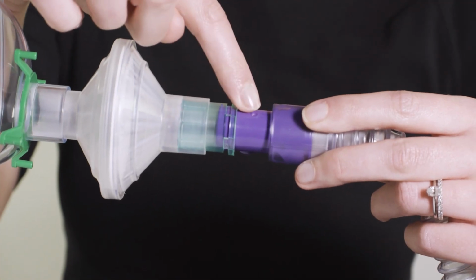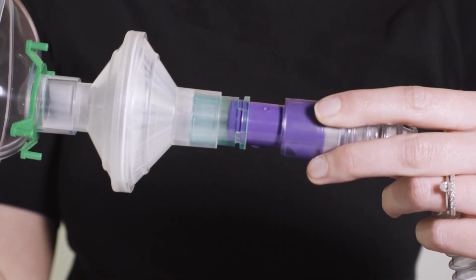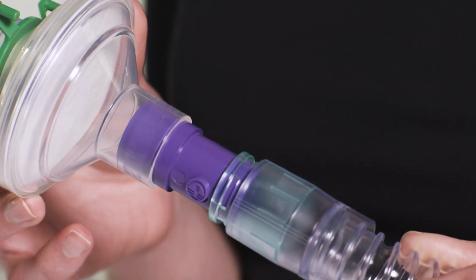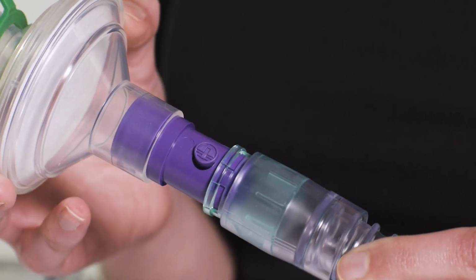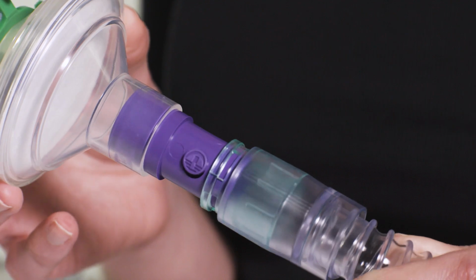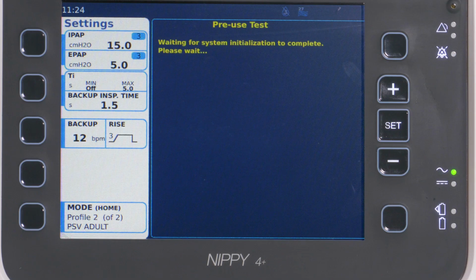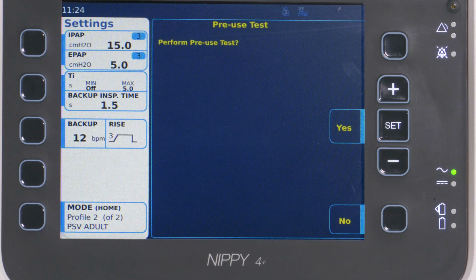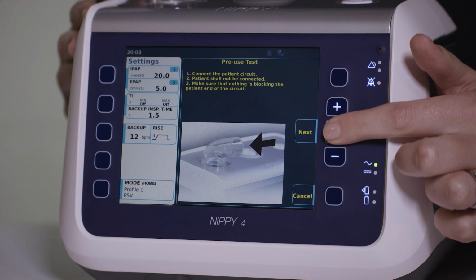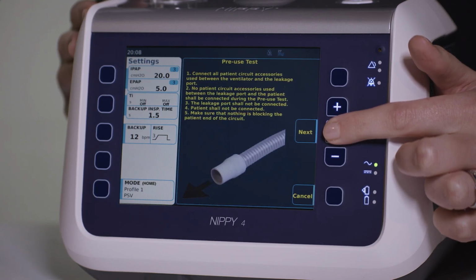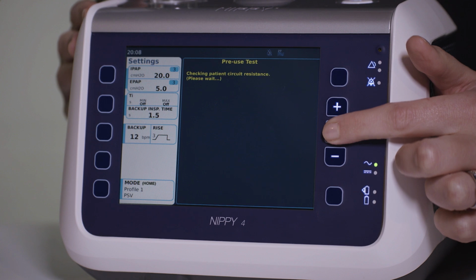You will also need to remove any leakage port, also known as an exhalation port, from the circuit temporarily for the purpose of completing the pre-use test. The circuit configuration must be totally sealed if it is to pass the pre-use test. Follow the instructions on the ventilator screen for full guidance throughout.